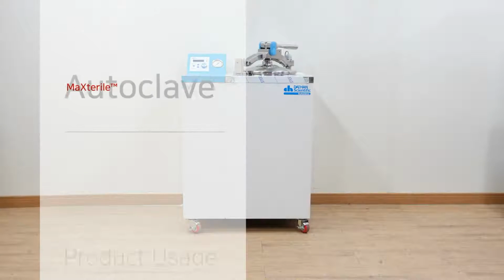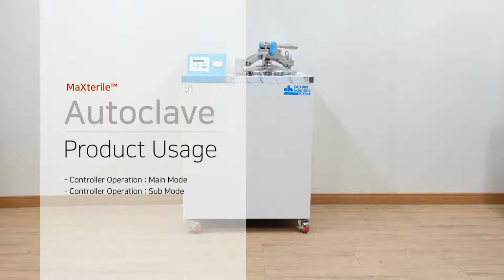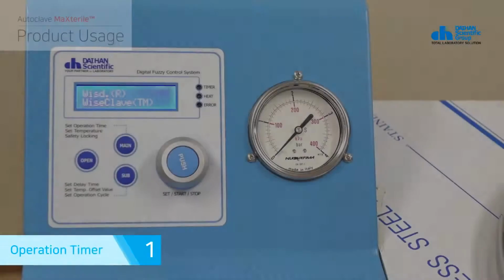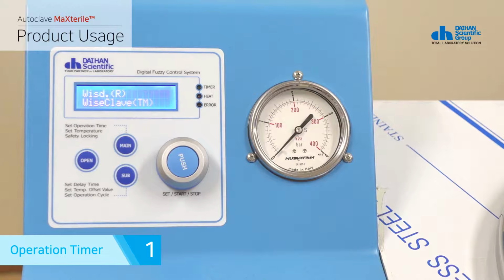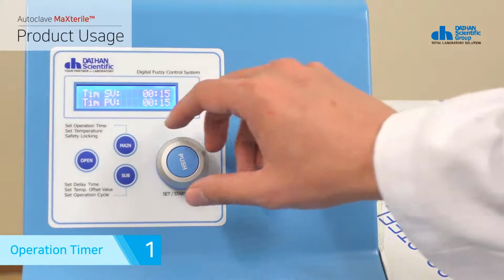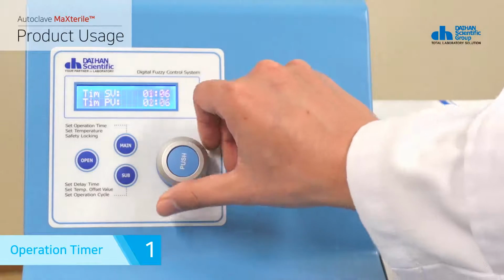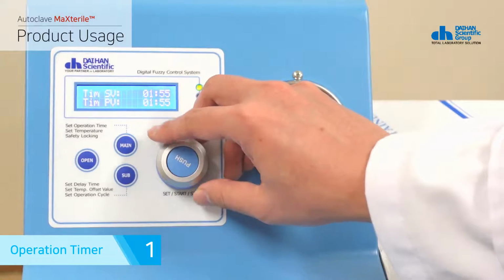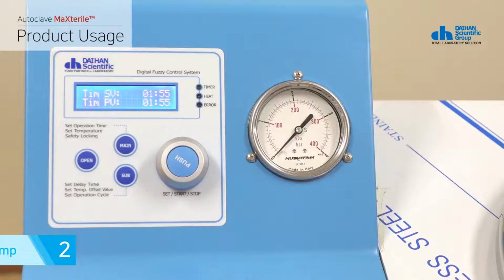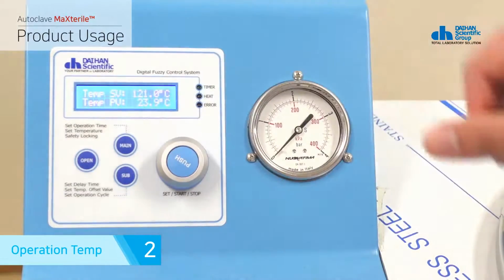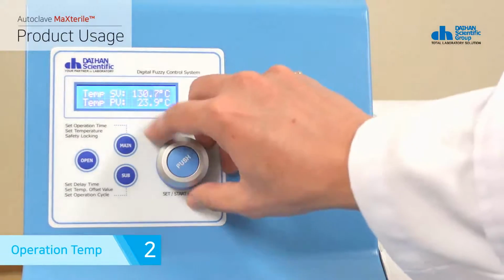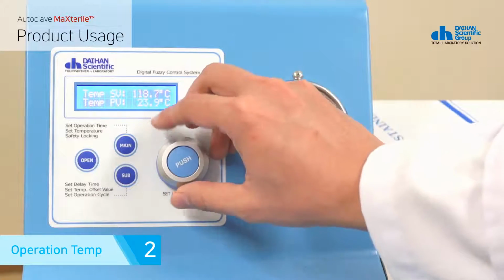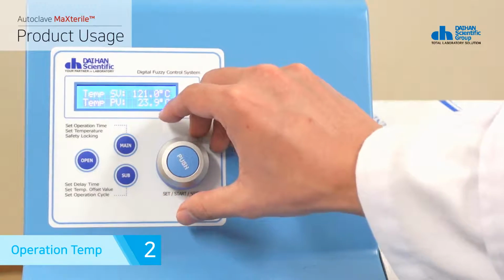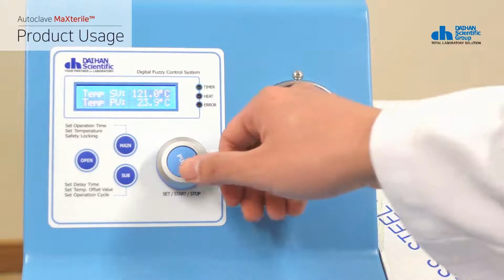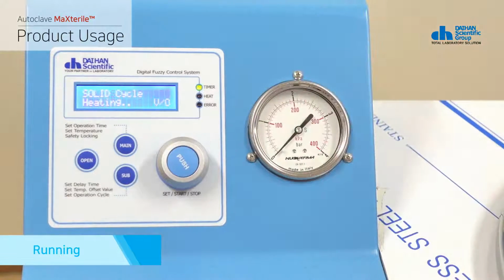The following is a description of how to use the product. Operation timer sets the time for sterilization. It counts after reaching the target temperature and can be set up to 99 minutes 59 seconds in 1-minute increments. When you press the main button in the operation timer, it switches to operation temperature. You can set the operation temperature's sterilization target temperature up to 132 degrees in 1-degree increments. After setting the time and temperature, press jog dial in operation temperature to start product operation.